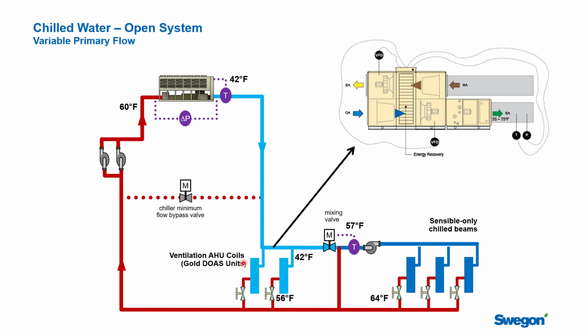And then down here, we have a chilled water loop that's servicing the primary air handling units. Usually this water has to be close to 42 or 44 degrees Fahrenheit because it has to do the dehumidification in the air handling units up above. We're showing two coils here. Just think of it as two air handling units. It's not like there's two coils in series. But this loop is about providing water cold enough to do the building dehumidification.